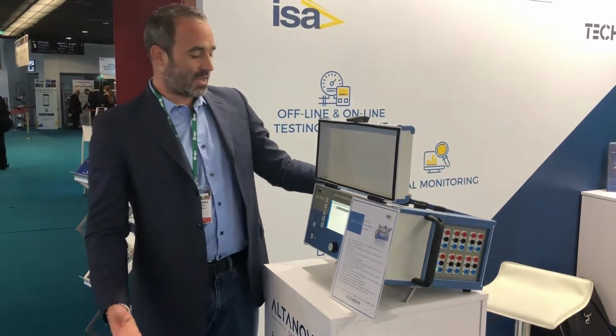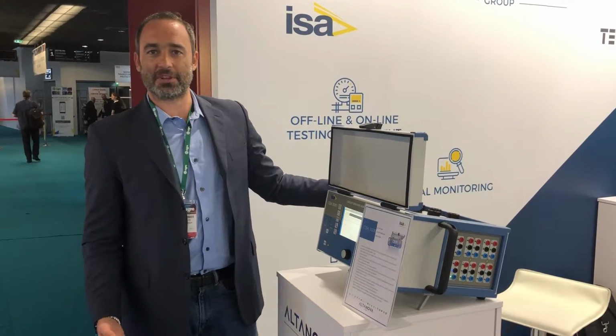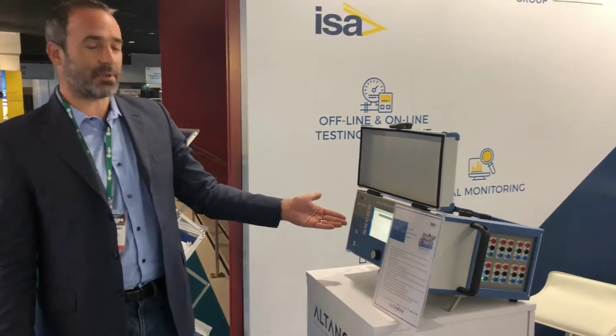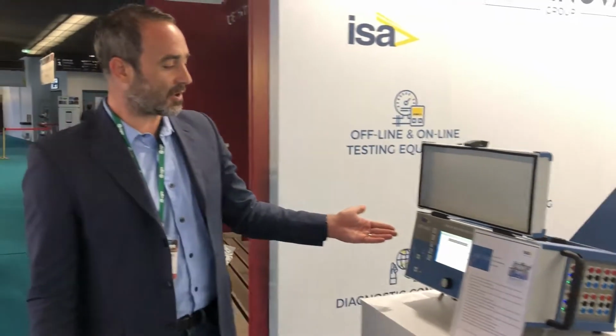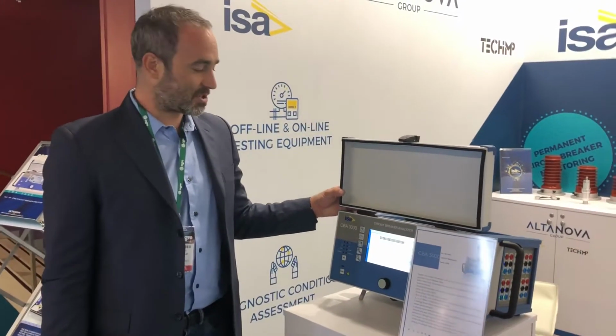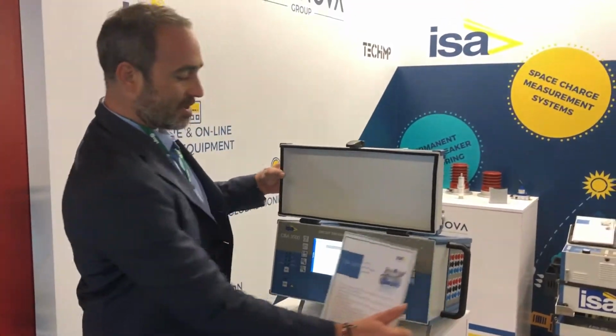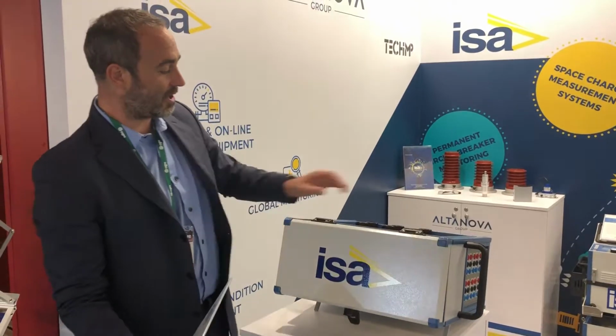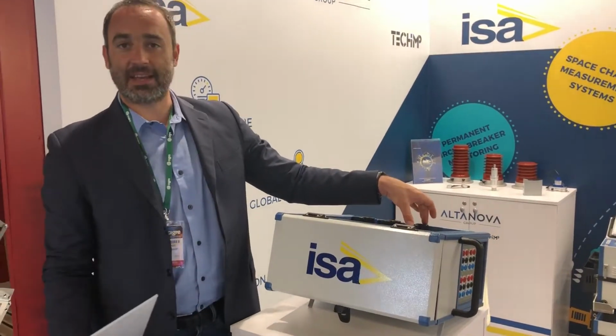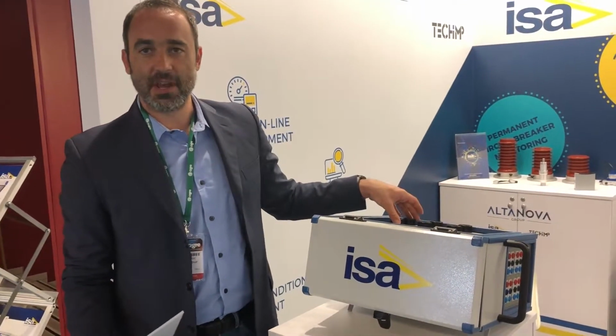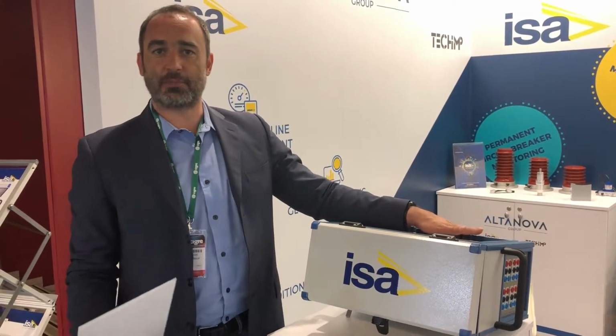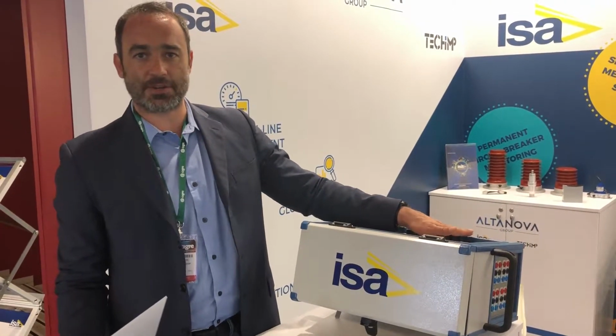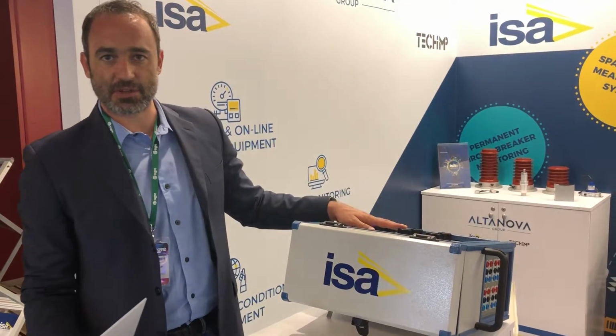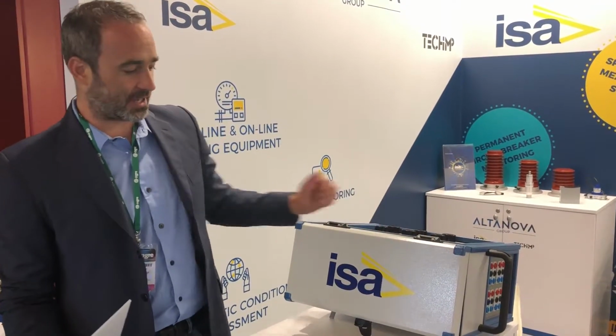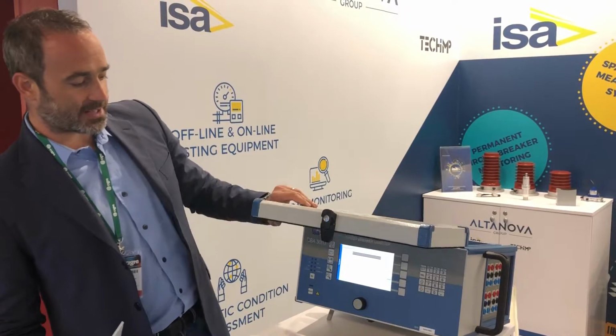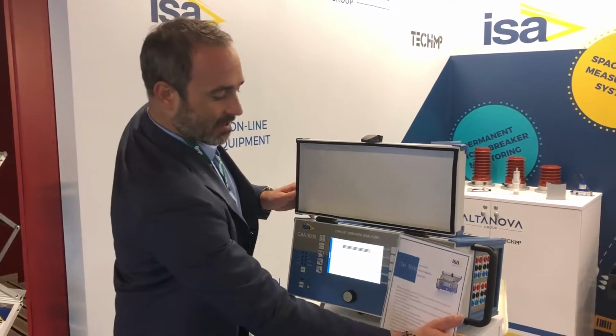This year we have decided to show you some of our newer devices. From ISA we have a CBA 3000, which is a circuit breaker analyzer, which has a special ability to do three-phase micro ohm meter generation. So in that case you don't have to change the connections with one connection. If your circuit breaker is grounded on both sides, you can measure the time and the resistance of your circuit breaker's main contacts. Circuit breaker analyzer we have here is a CBA 3000.